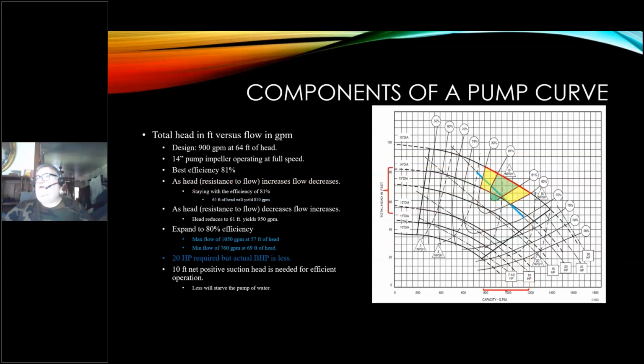So if I said the design was 900 GPM at 64 feet of head, I want to get into the green zone as best I can. The yellow zone's okay. Down in this horsepower, about a 20 horsepower motor, really, that's the biggest horsepower I can get. If I choose the 14-inch pump impeller at full speed, best efficiency is 81%. As head increases, resistance to flow, the flow will decrease. If I try to stay in that 80%, 81%, the dark green area is basically where I'm going to end up. Now, I could get into this orange area. Again, I'm operating in this zone, but my best selection is probably this 14-inch diameter, because it covers the entire range in head in feet and my entire range in flow.